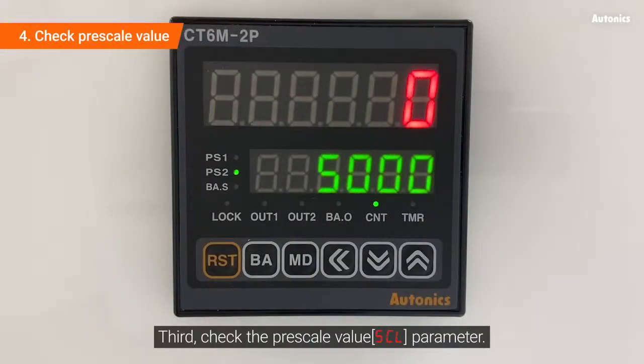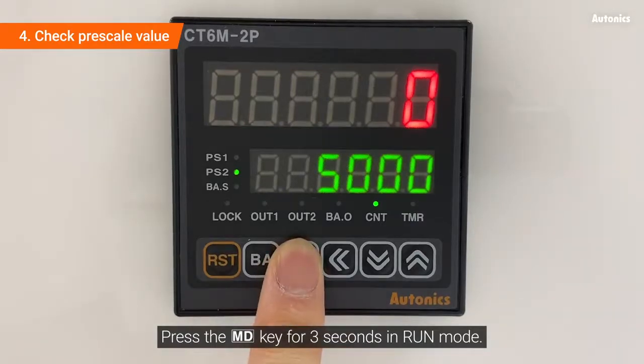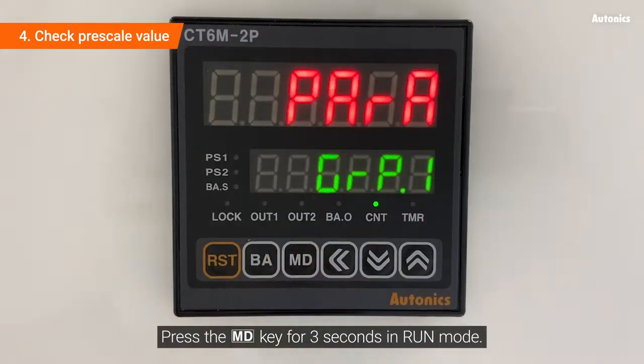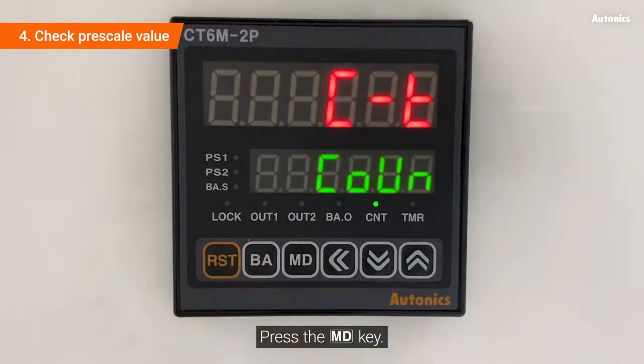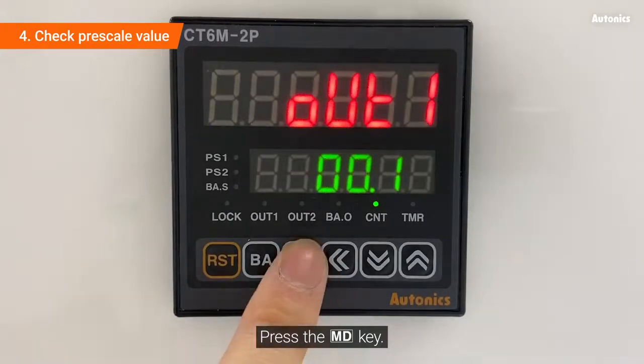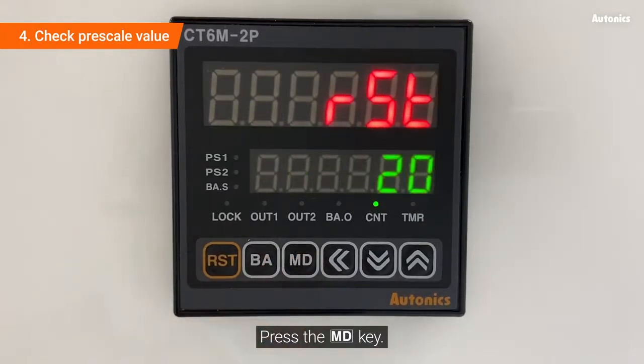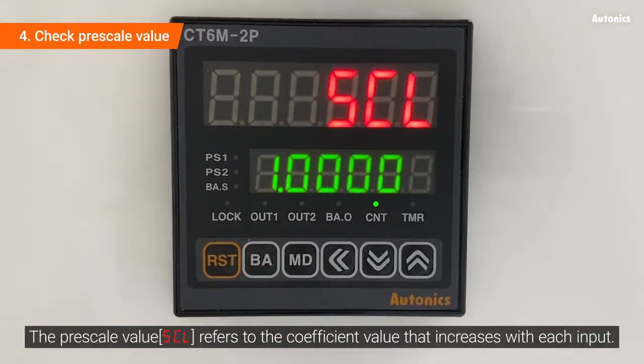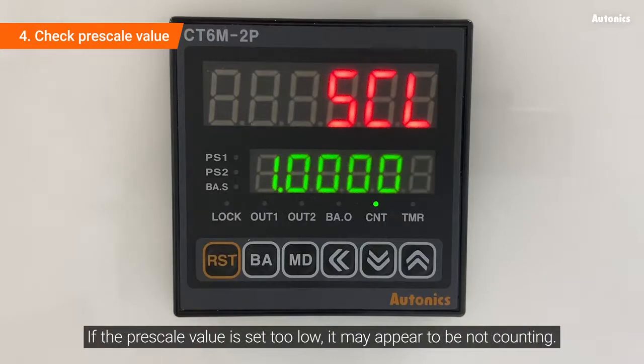Third, check the pre-scale value SCL parameter. Press the MD key for 3 seconds in run mode. Press the MD key. The pre-scale value SCL refers to the coefficient value that increases with each input. If the pre-scale value is set too low, it may appear to be not counting.